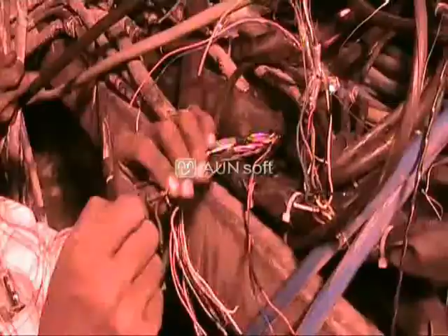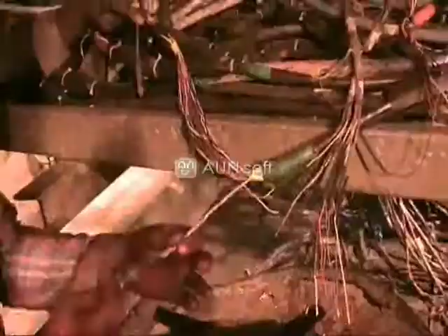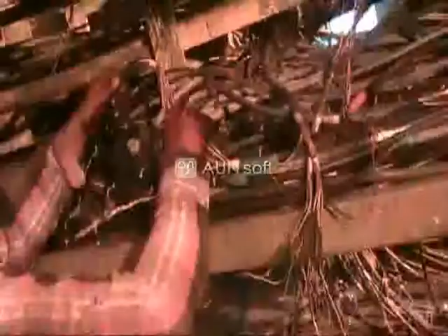After getting the new joining cable with the tag, the crimping team ensured double sleeves for each core. The crimping process continued with crimping, shield crimping, dressing the cores, cable sleeve dressing, and final dressing on the cable tray. Ensuring perfect crimping and avoiding disconnection in case of any disturbance on the cable was the primary task of the crimping team. All the cables were shielded, so after crimping the individual cores, the shield wire was crimped with lesser length than the core length, so that dragging or any other disturbance to the cable joint would first break the shield wire. Sufficient extra length was provided to the core cables so that during disturbance, the joint would not cut.